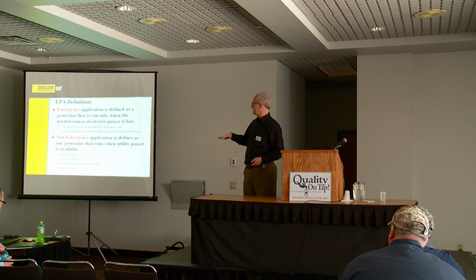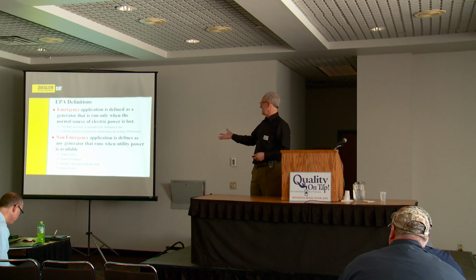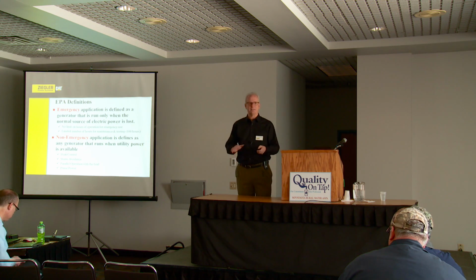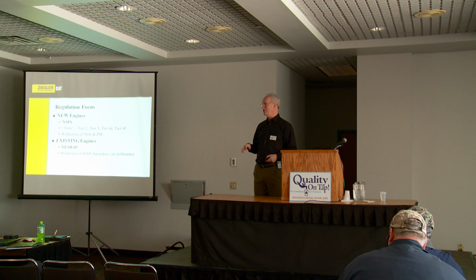There are some other things that would be classified as non-emergency. Sometimes casinos, if they have power glitches during thunderstorms, might turn on their generator when a thunderstorm is coming into the area just to make sure they don't have any power glitches. That would be non-emergency. Utilities running their generators to put power on the grid, that's non-emergency. But for most of us here, if you're on a utility program, if you're getting a discount on your utility rates because you have a generator that they could call to run sometime, that means you're non-emergency as far as the EPA's definition goes.